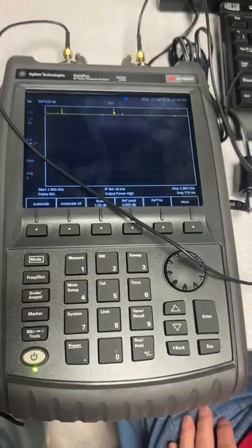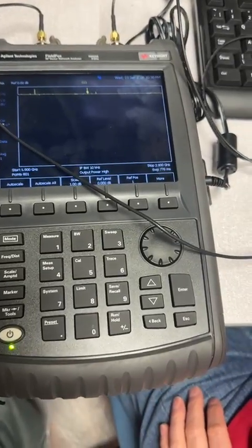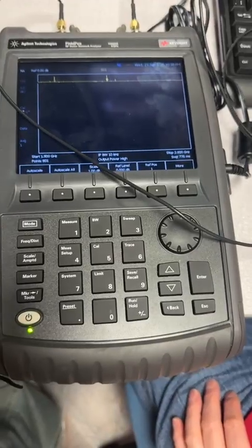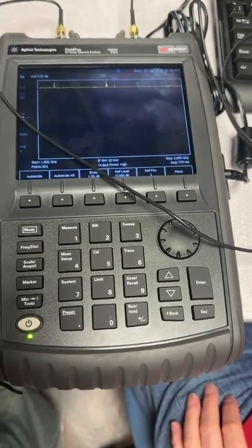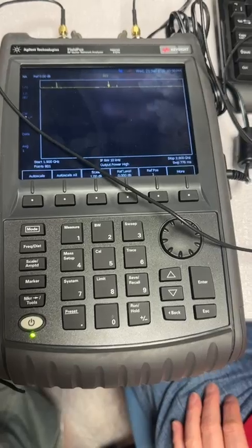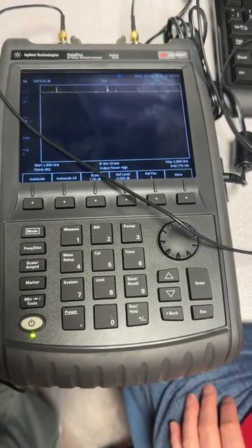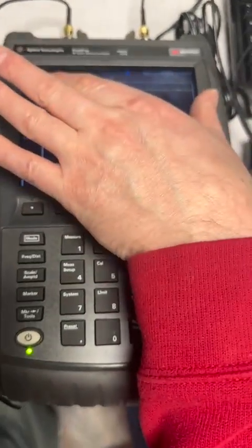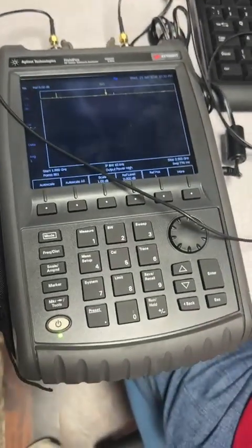Because you can't realize precisely an open circuit or a short circuit, because of the parasitics, because of the nature of RF signals. You've got reflections with a short circuit, haven't you? So it's not a perfect short circuit. It's never perfect. And you're trying to do that calibration over a wide spectrum of frequencies, not just at one but multiple. So that's why we need the cal standards.